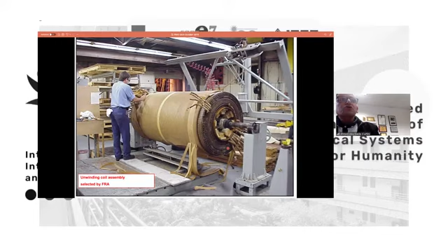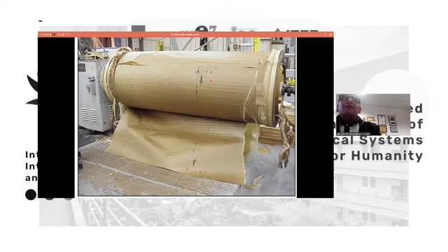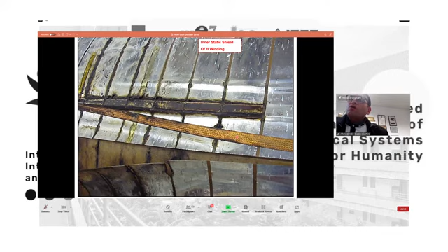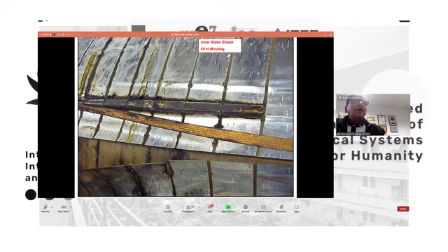Look, when we started to unwrap it, we found carbon tracking spots here, which means something was happening inside. There's sustained arcing or partial discharge underneath. And when we completed unwrapping the winding, we found that the static shield of the high voltage winding was loose. And that was the cause of the sustained arcing or partial discharge. The transformer looks normal and was working normally during operation. But if you leave it, you may end up having a fire. If you don't notice that there's something wrong, this sustained arcing may lead to fire, catastrophic failure.